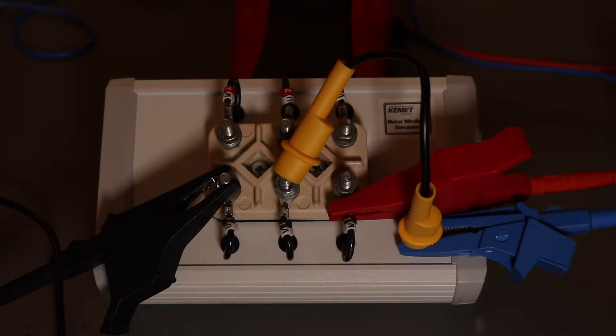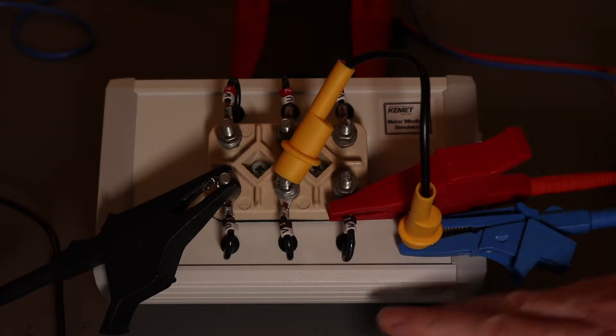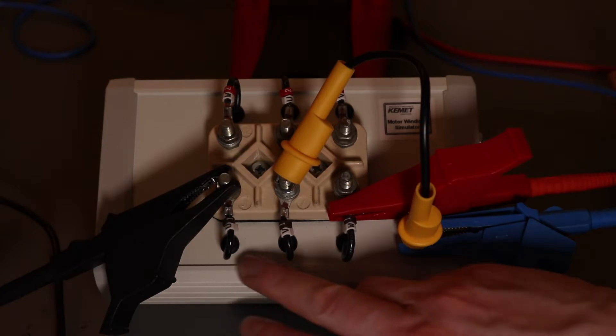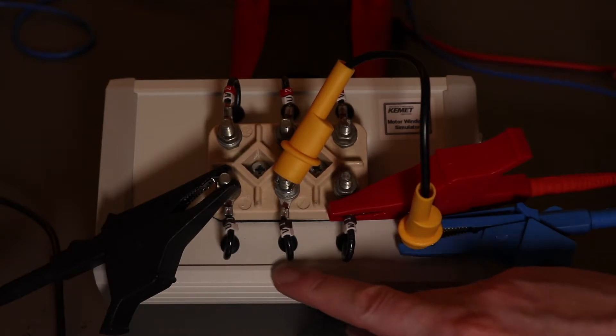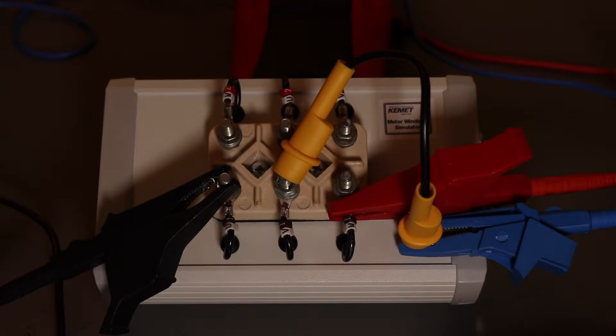That's another way of using a guard terminal on an insulation tester to get specific readings just for insulation values for a specific winding to winding insulation or winding to earth. It's probably something you would ever do on a very large motor that's got a lot of value to it to find out specifically what is wrong with it.